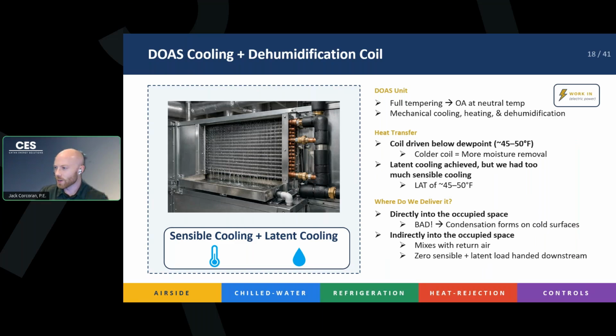And then we have our DOAS cooling with dehumidification, right? And so the primary purpose of this DOAS unit is to dehumidify, right? On the psychrometric chart, we're moving that heat down vertically, right? We want to get rid of the moisture as much as possible, so that if we dump it into the space, you're not going to have any humidity issues. Or if you dump it into another coil, then this downstream coil doesn't have to worry about humidity. It just has to temper the air temperature, dial it in per zone.